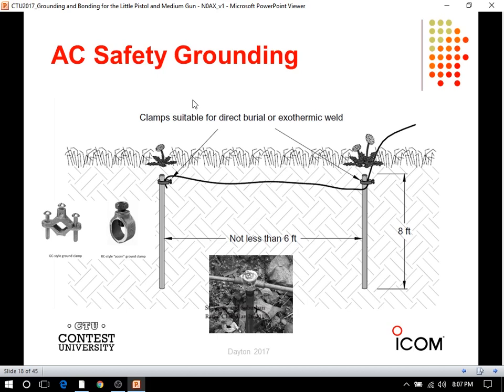If you look down here, you can see this little crusty looking thing. That's what's left after you use a one-shot. The one-shot is a thermite welded thing - it's a powder. You get a little crucible, put it on your ground rod, put the ground wires in from either side. There's lots of different variations on it - CAD weld. Then you put the starting powder in there, spark it or use a sparkler, and you stand back. As they say: place on ground, light fuse, retire quickly.